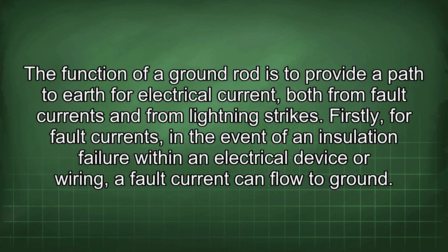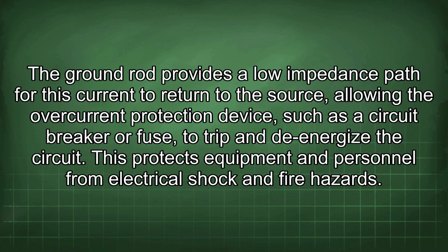The function of a ground rod is to provide a path to earth for electrical current, both from fault currents and from lightning strikes. Firstly, for fault currents, in the event of an insulation failure within an electrical device or wiring, a fault current can flow to ground. The ground rod provides a low impedance path for this current to return to the source, allowing the overcurrent protection device, such as a circuit breaker or fuse, to trip and de-energize the circuit. This protects equipment and personnel from electrical shock and fire hazards.